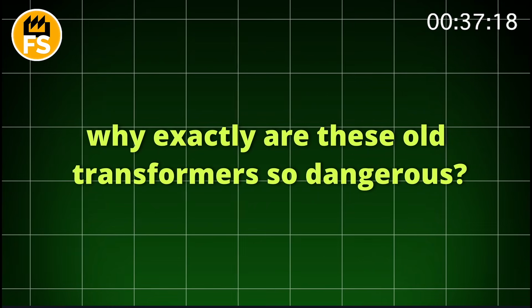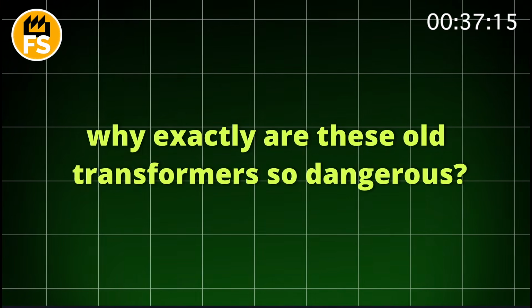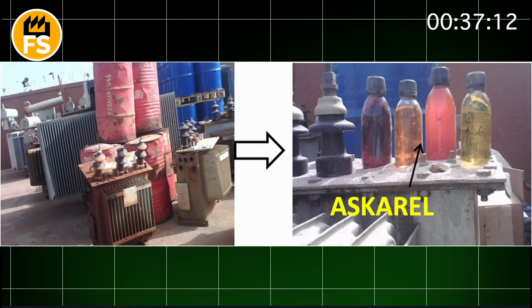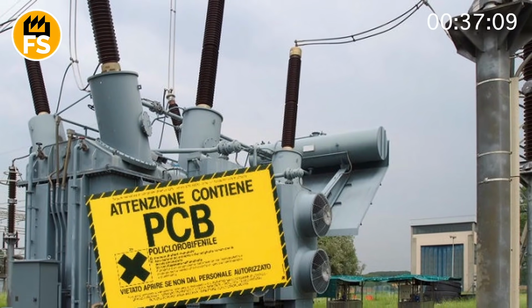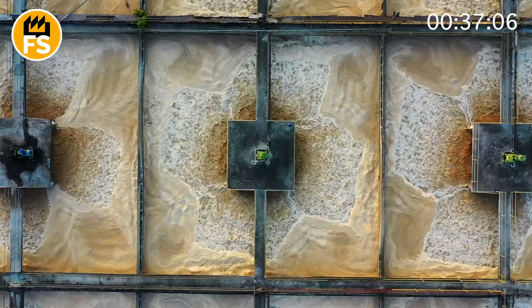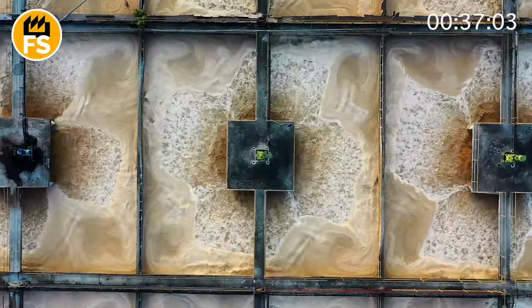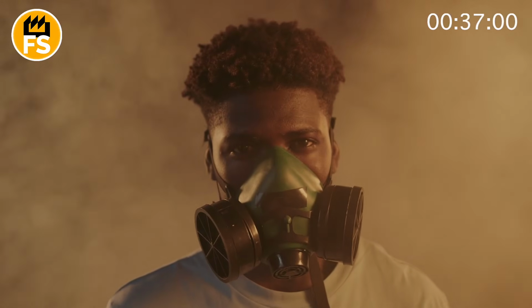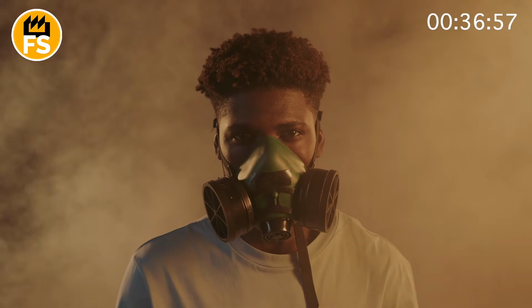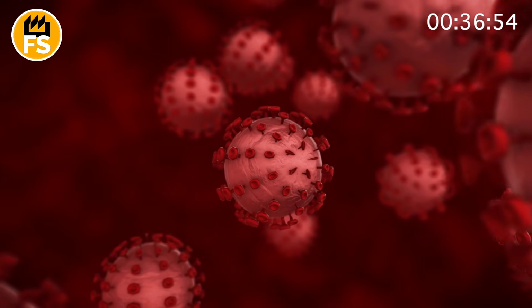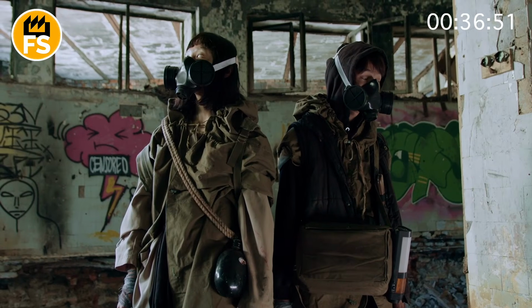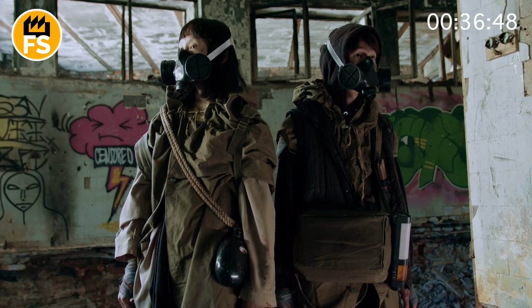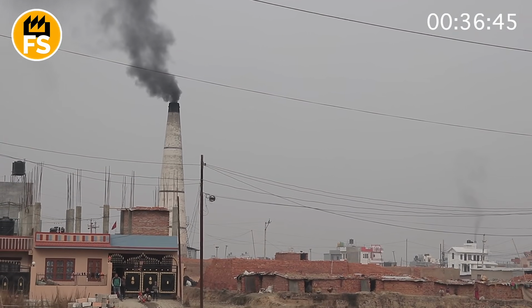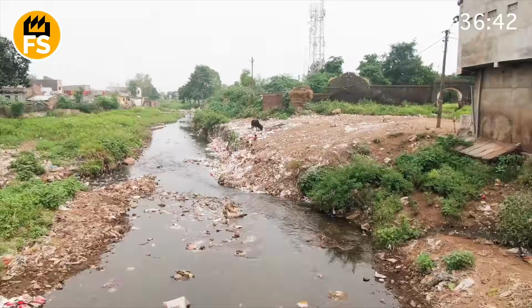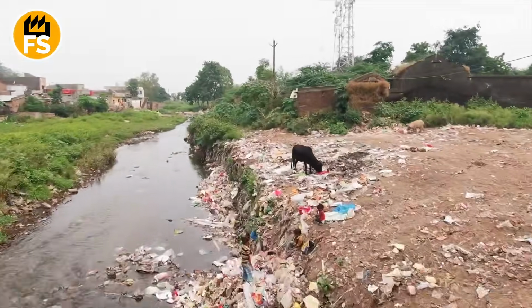So, why exactly are these old transformers so dangerous? For decades, many relied on a coolant liquid called ascarel, which contains polychlorinated biphenyls, or PCBs. These chemicals are terrifyingly persistent in the environment. They don't break down easily, and they are highly toxic to humans and wildlife. Even a small leak from a neglected unit can contaminate soil and water for generations. Modern transformers use safer, non-toxic oils, but the legacy of PCBs in older units means they cannot simply be scrapped like regular metal waste. They demand specialized, heavily regulated facilities designed specifically to handle these hazardous materials with extreme care and containment.